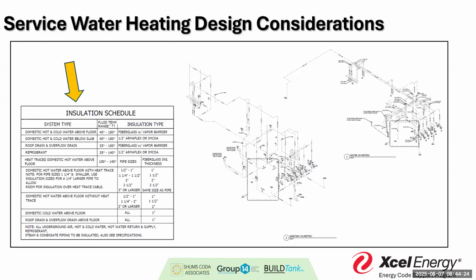It sounds like a stupid note, and I hate to put it in there, but I understand you're going to insulate these pipes with different insulation sizes. What I need to hear is that you understand there's a minimum thermal resistance value associated with these designs, whether it's R3 or whatever minimum, not just 1 inch. We want to recognize it's thermal resistance, not just depth of insulation.